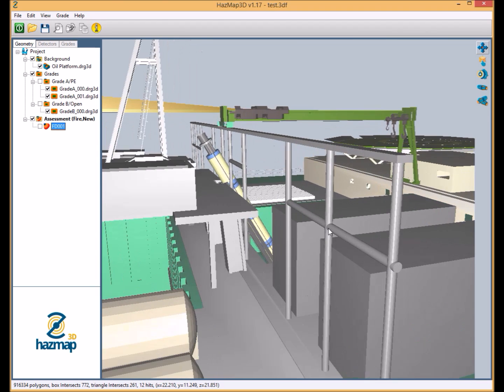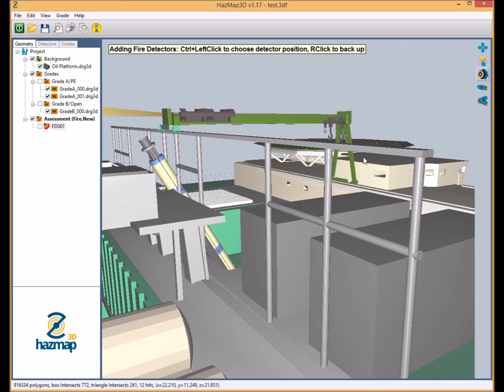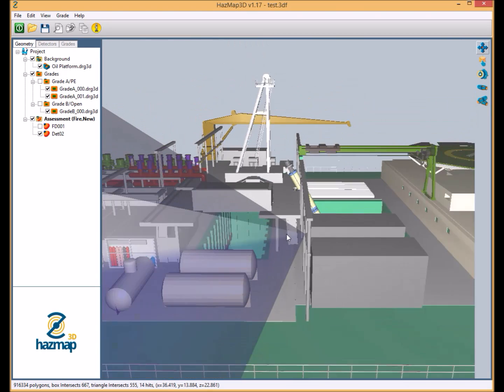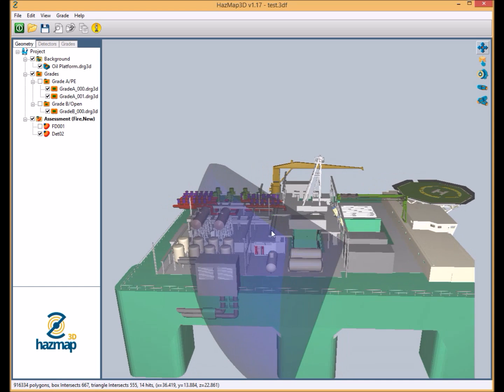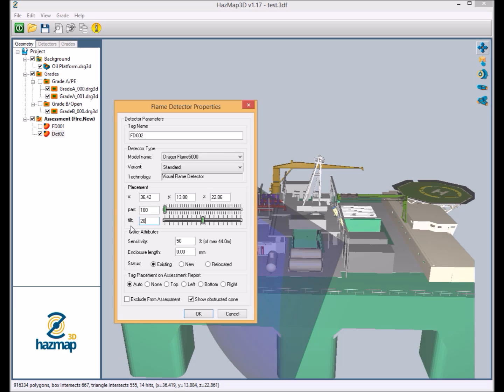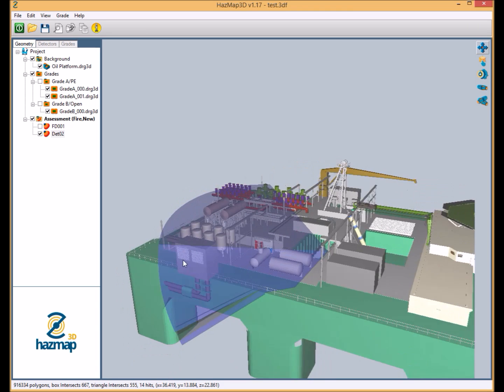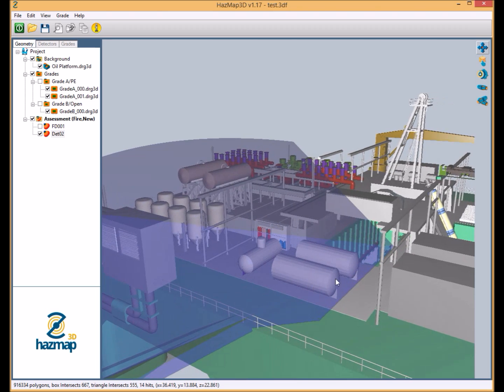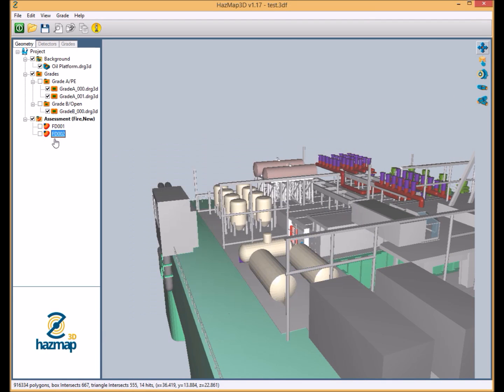We're just going to add in a second device on the other side. Okay, the software has obviously remembered that we're using the Flame 5000 at 50% sensitivity. So again, making the user experience as easy as possible. And we're going to put in an appropriate pan and tilt of the device, 20 degrees down from horizontal. And that looks okay.